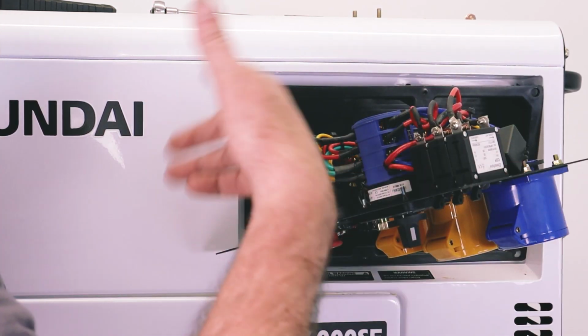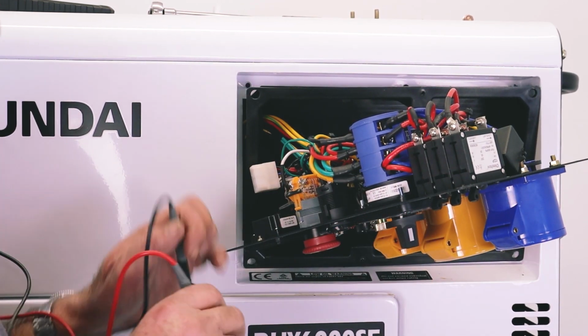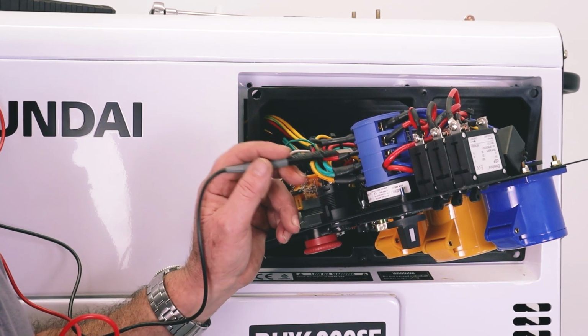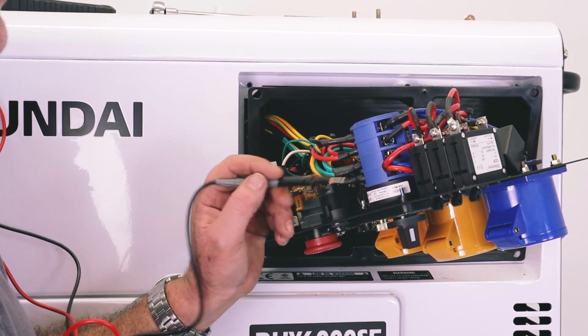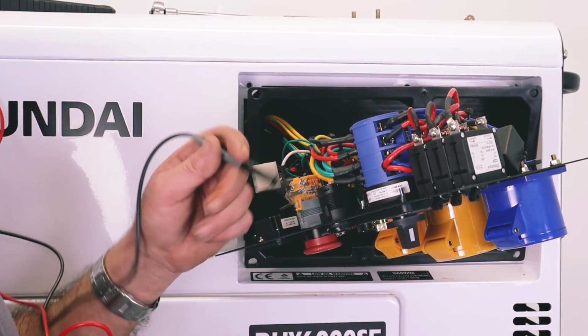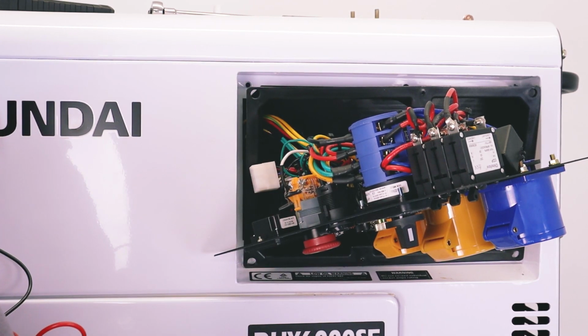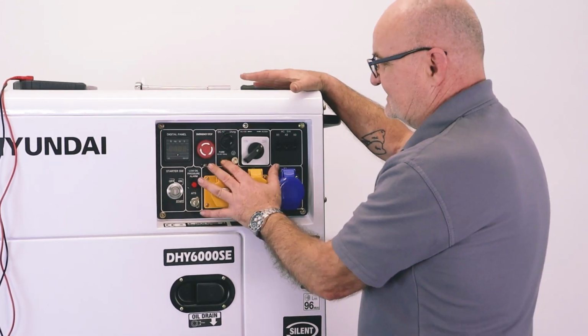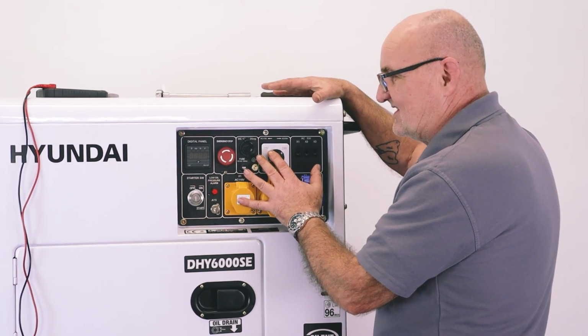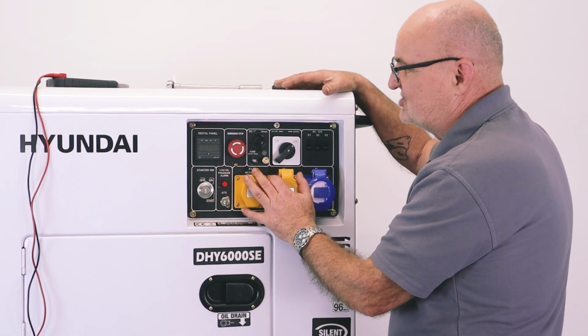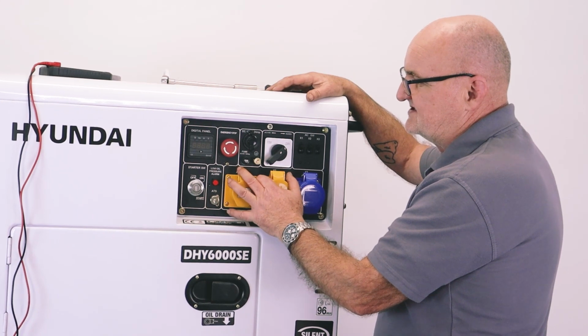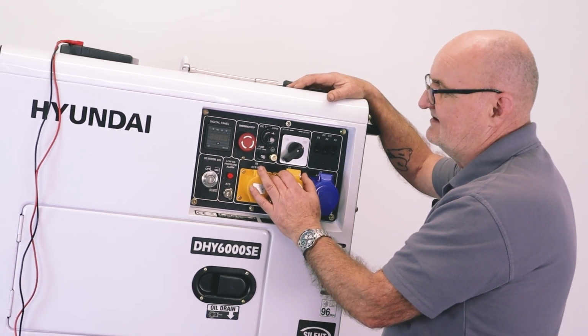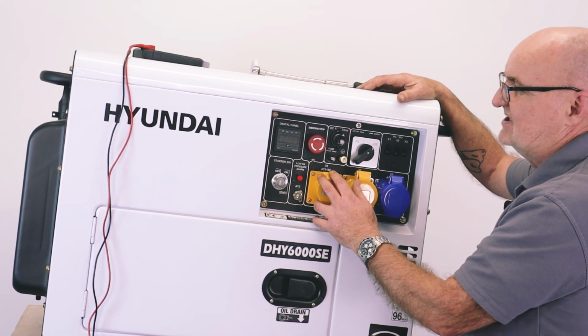So at this point, we need to be switched off again, and we can refit the control panel. That's the scenario that we haven't got 115 here, and we haven't got 115 here. We know that the problem lies deeper within the generator itself. So we've ascertained that the problem isn't within the control panel, it's deeper within the machine. Now there's a couple of scenarios here. 0 reading on here, that tells us it's in the machine.